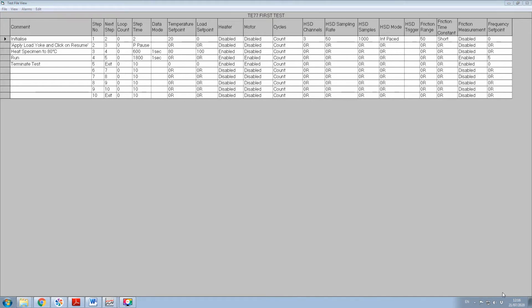This column includes the facility to include loops and calls to subroutines. Right-clicking on the Next Step box will open the parameter window for the current step. In this case, if I click on the Next Step box for step number 1, the parameter window shows Go to Step 2, which is the next logical step, and is entered automatically when the Next Step button is clicked. I can, however, manually enter a different go-to step, should I wish, thus creating a jump.